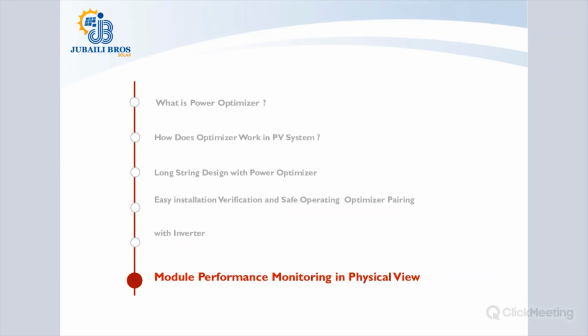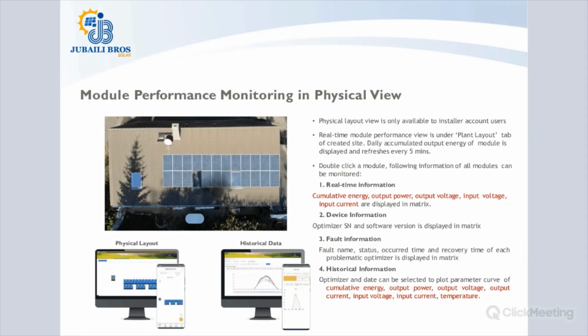Finally, let us move on to the module performance monitoring in the physical view. So how to remotely monitor the performance of the modules at the module level, not at the string level. So this is module performance monitoring in physical view. Here we see an example of a PV installation on the roof, and we also see shading, right? We see some of the panels are shaded.